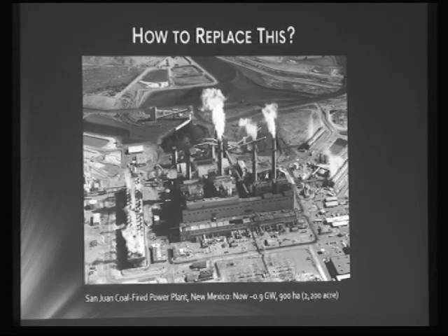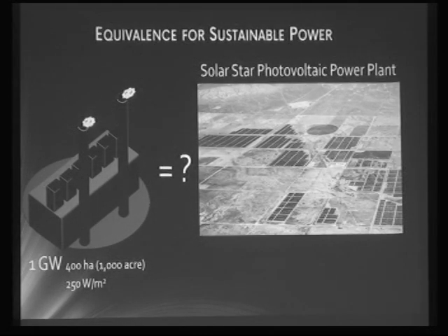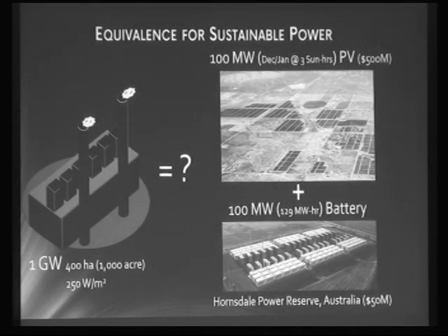This facility, outside of California, currently feeds about one gigawatt of baseload power into the Californian grid. What's the exchange rate from coal or gas-fired to clean solar energy? Solar Star is the most productive solar PV farm in California — its capacity is nearly 580 megawatts, but averaged over a year that's only 175 megawatts, and in January and December the average output is only 100 megawatts.